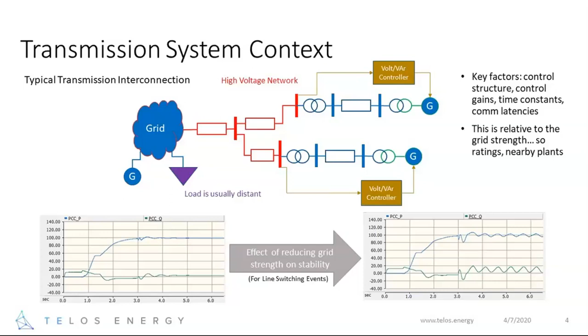One of the things we focus on is the weak grid issues, commonly quantified by short circuit ratio or the grid strength. You can see in the plot on the bottom left, a normal behavior where, in this case, a line switching event while doing Volt-Var control produces a little bit of a second order ripple that is damped out quickly and you have no problems. For the same control, everything else constant, but a change in the grid, particularly in the grid strength, for instance, a transmission contingency that weakens the grid, for the same line switch event, you can now see some of that unstable behavior starting to manifest in terms of sustained oscillations that are not damped out.